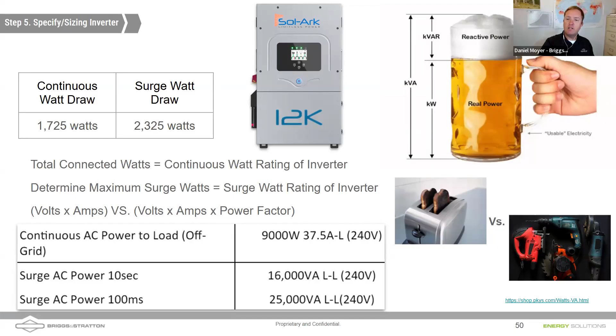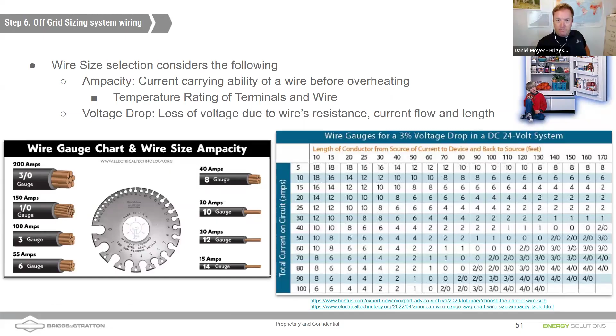If we're doing some DC loads - this is my example where I get to talk about Sunfrost again, top right corner is an old picture, that guy looks as old as me in it. When we have DC conductors, especially at lower voltages like 12 or 24 volt, a Sunfrost uses 10 amps at startup when that surge kicks in, though it uses a lot less while running.